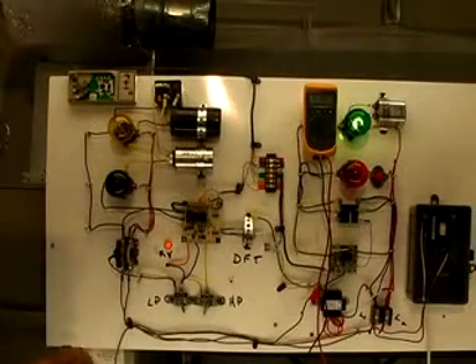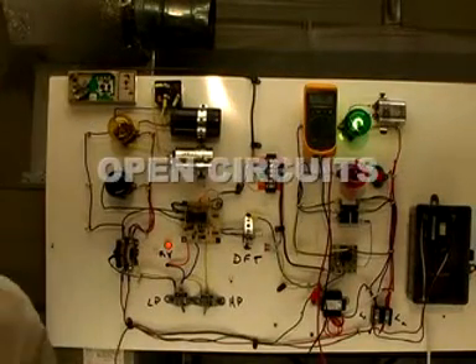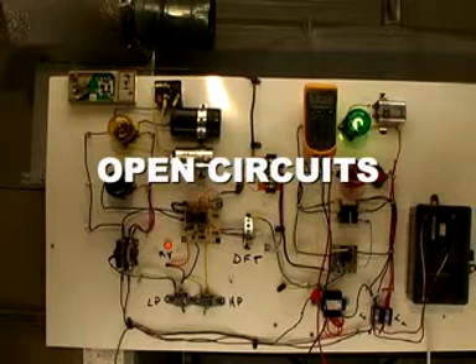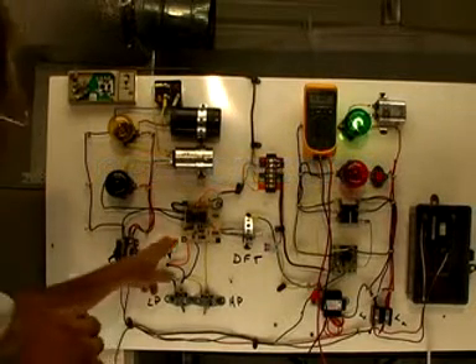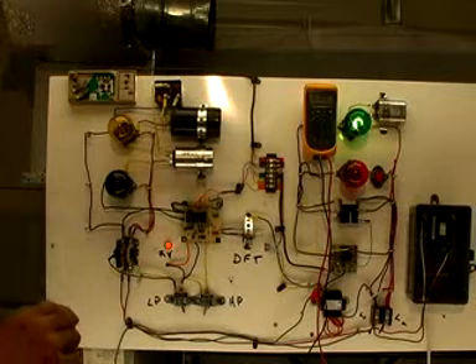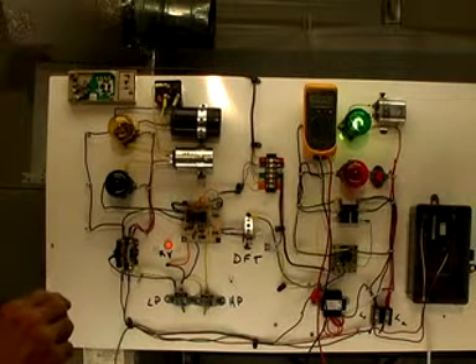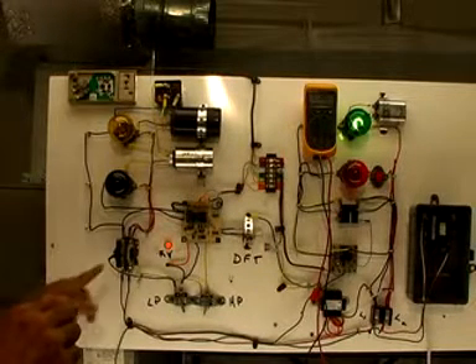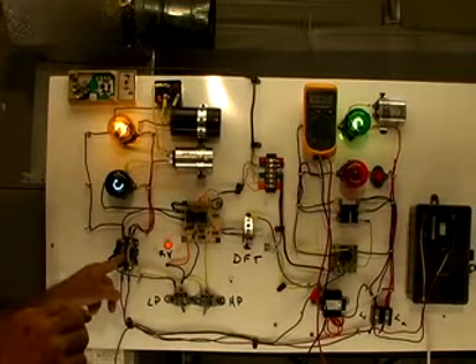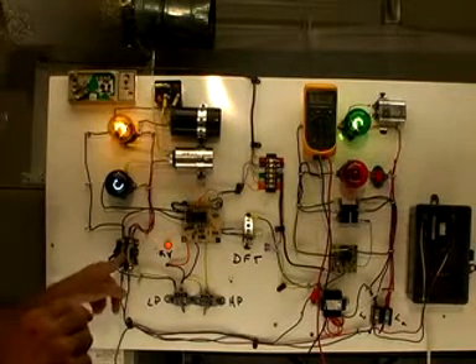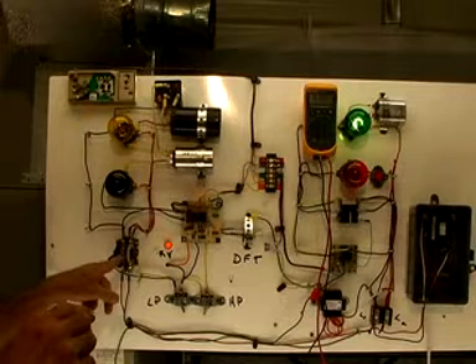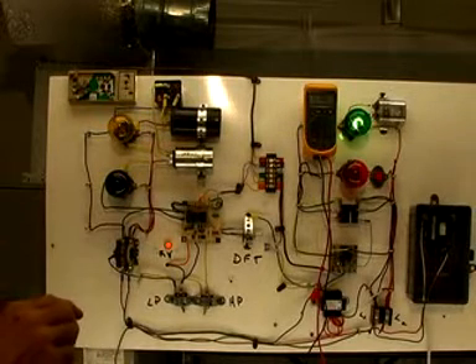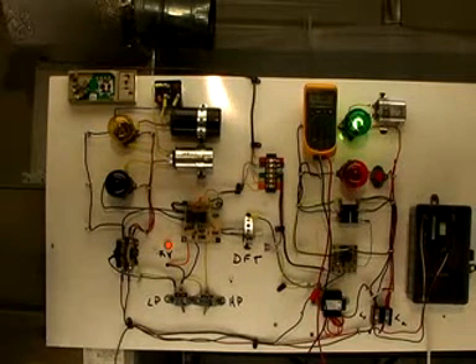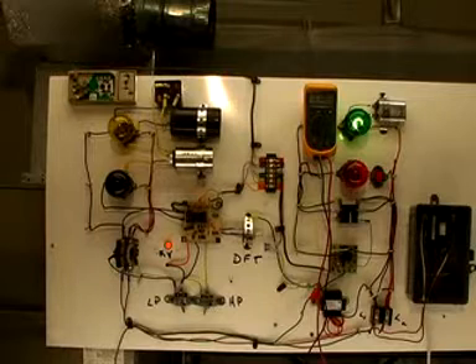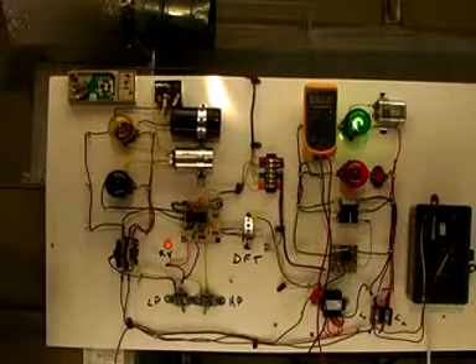Okay, first situation: we're on the service call, the blower's running, but the condensing unit hasn't come on. We see the reversing valve light is energized, but the contactor just hasn't pulled in. Your first tendency is to come over here and push in the contactor with your finger, or something non-conductive is smarter, and see if it comes on. Then you know you don't have a high voltage problem. So at this point you've got to get the meter out and start checking to see if you've got voltage coming in on the Y circuit.